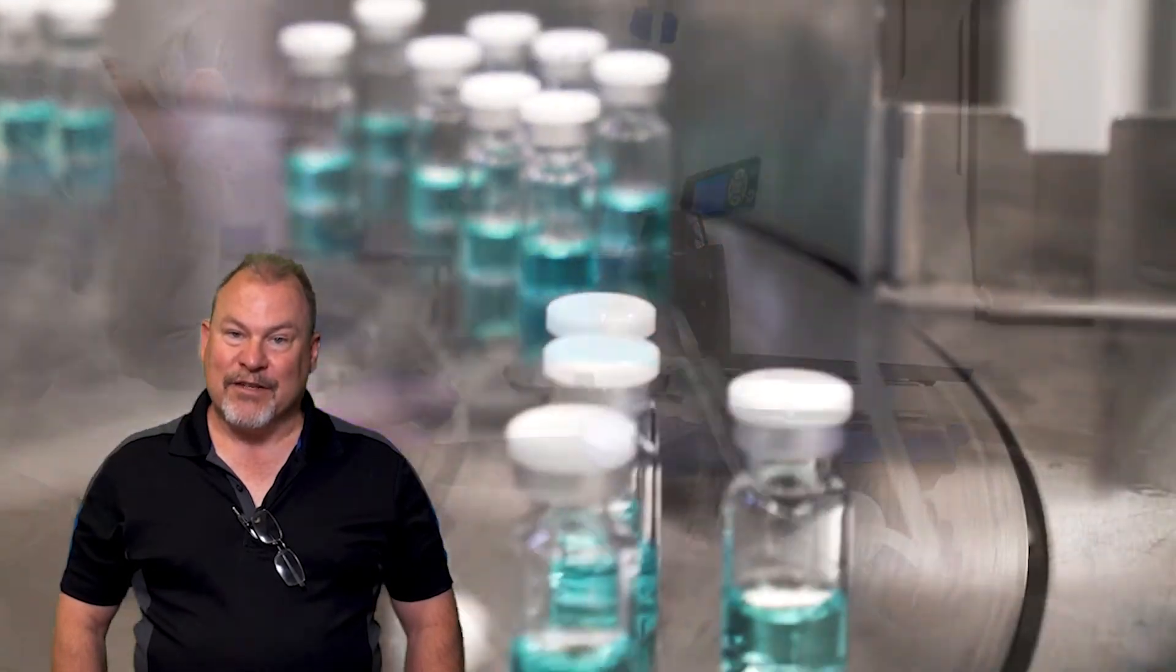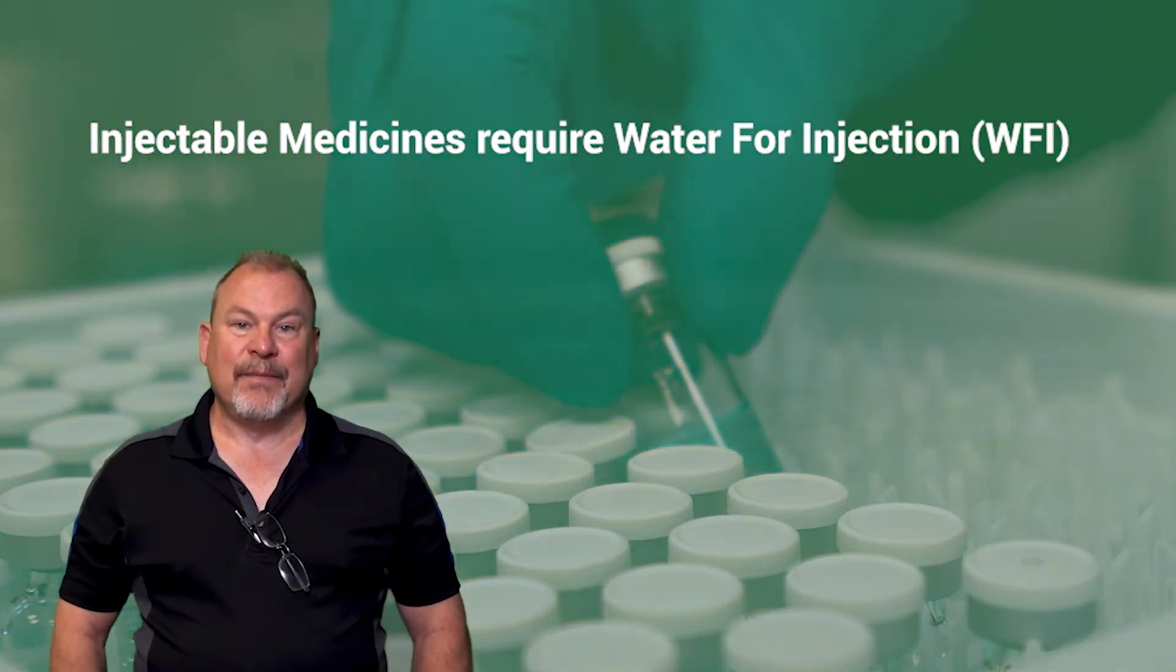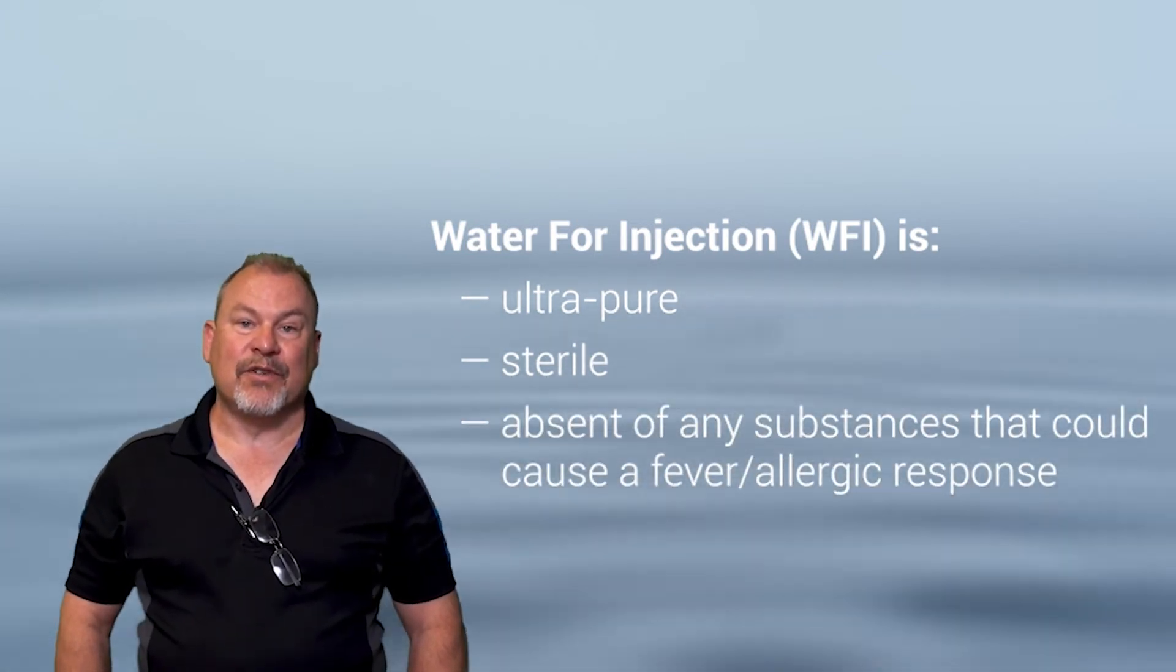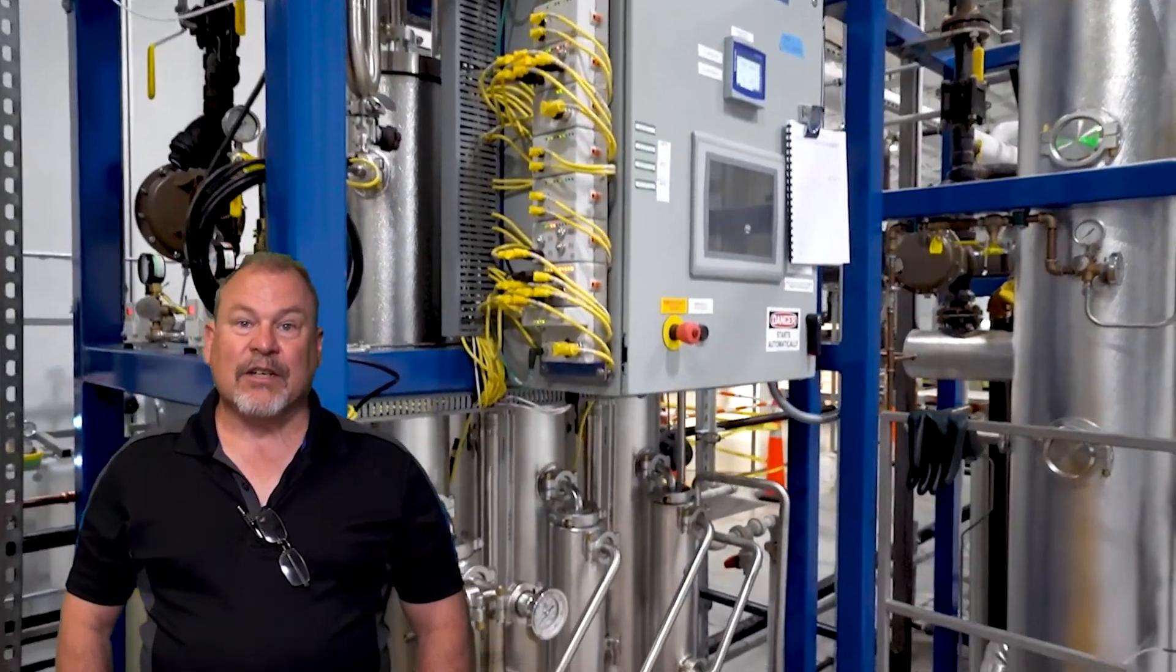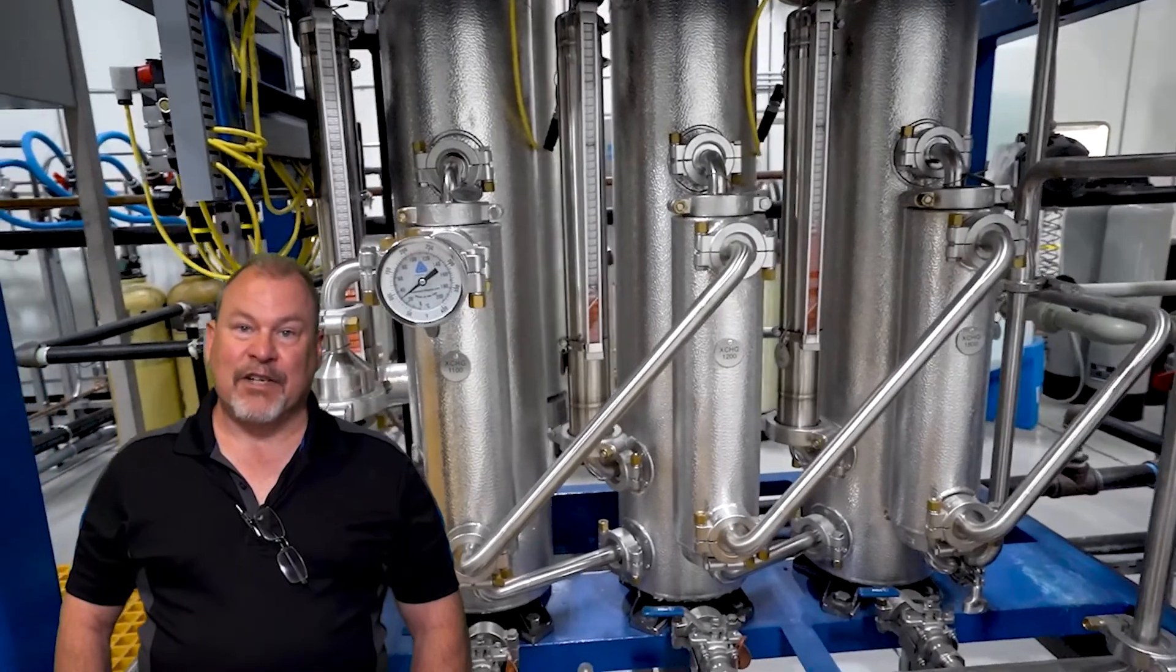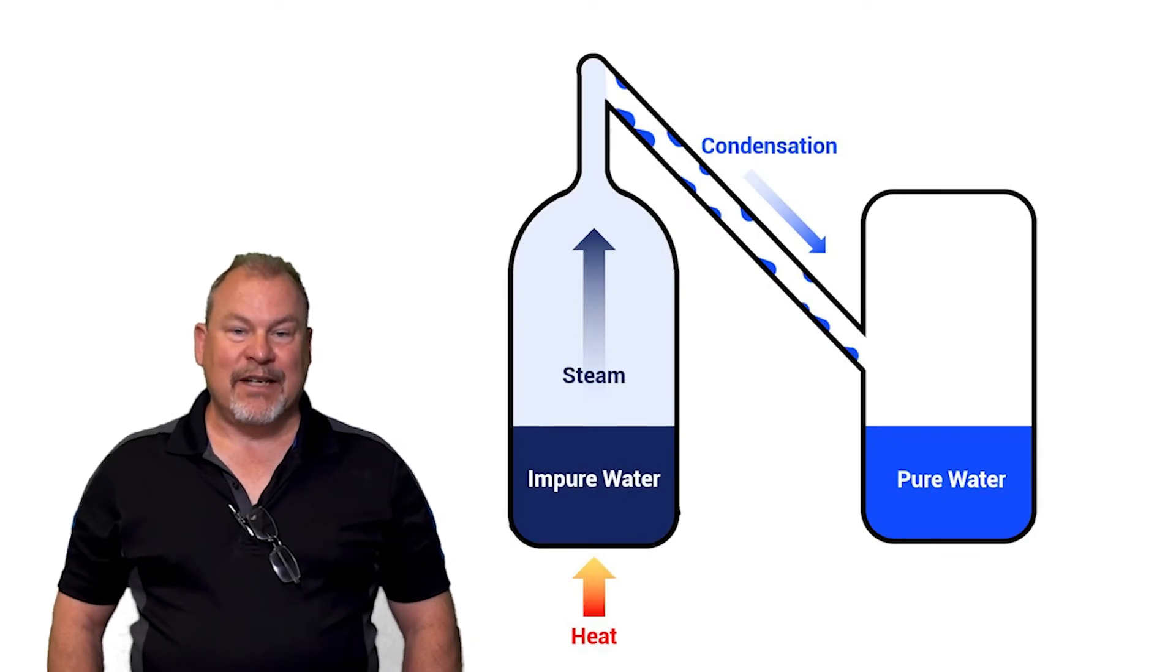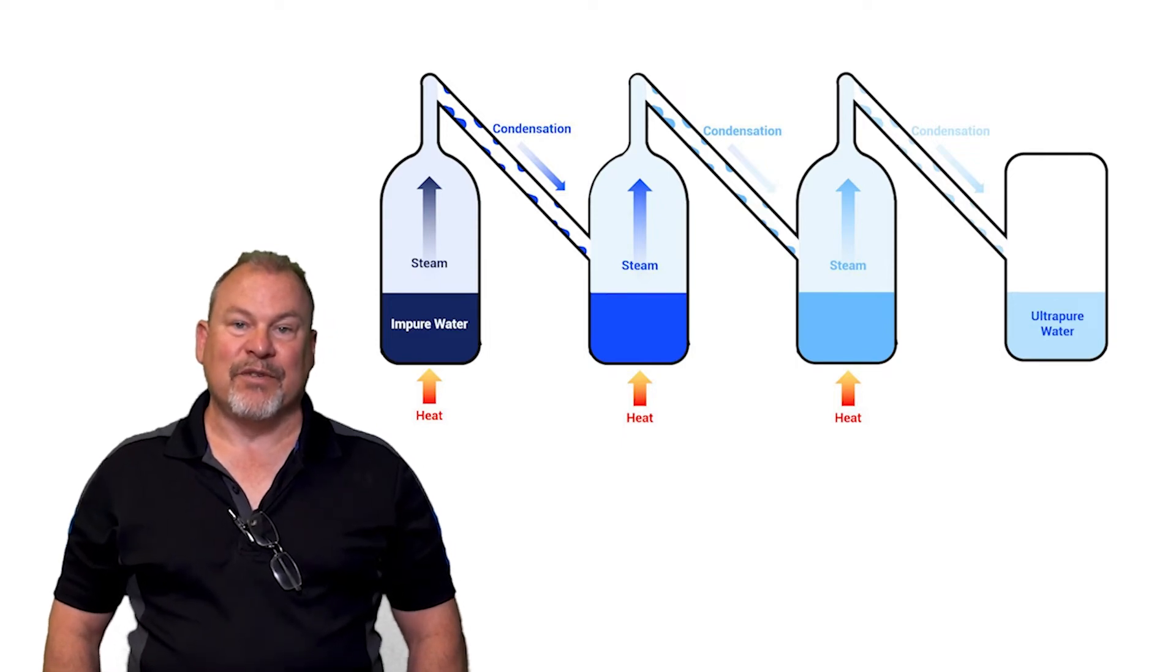Therefore, injectable medicines require water for injection. This is water that is ultra-pure, sterile, and is absent of any substances that could elicit an allergic response or a fever. We prepare this ultra-pure water on site. Currently, you are looking at our WFI system, which represents approximately a $2 million investment to be functional. That does not include validation activities. This system heats purified water until it becomes steam, then the steam is condensed. This process is repeated two more times to ensure that the water we have at the end of this treatment is ultra-pure and can be injected into a patient without making them sick.